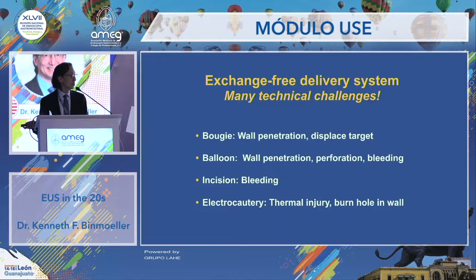So that inspired me to think about a different kind of platform that would minimize the coagulation effect and maximize or optimize the cutting effect. And that led to the development of the hot Axios. You can see these are micro wires that run along the sides in a radial fashion of a bougie-shaped ceramic tip. It's very hard and firm, and these wires then converge at the very tip like this in a circular fashion, so that we concentrate the electrosurgical current along a very small surface area. It's only 3% of the surface area of this tip here.